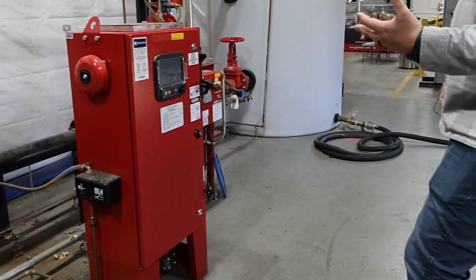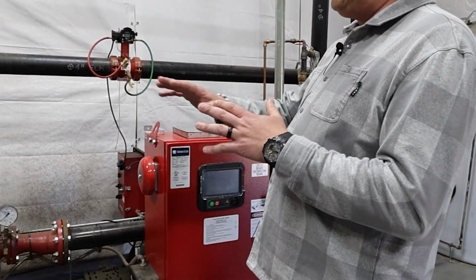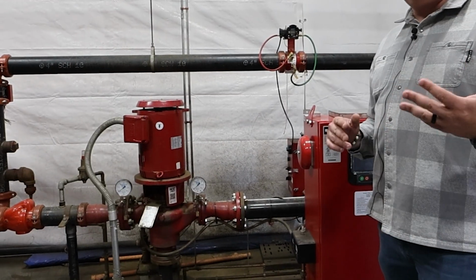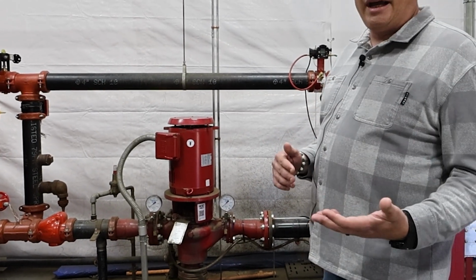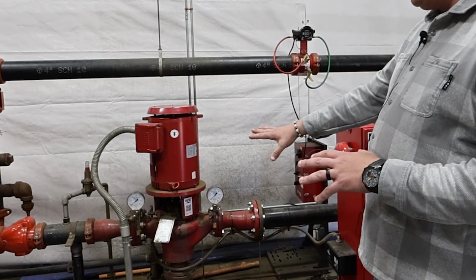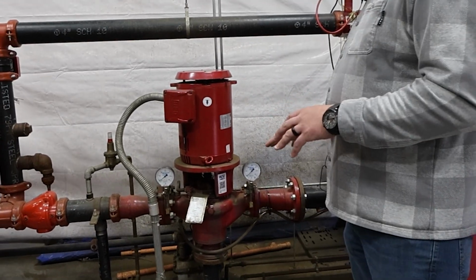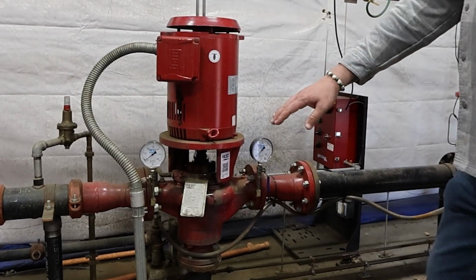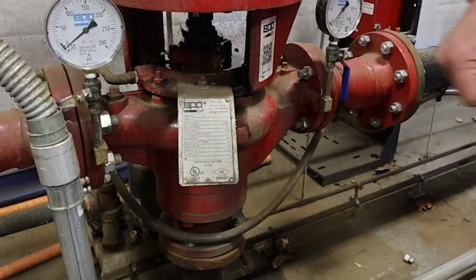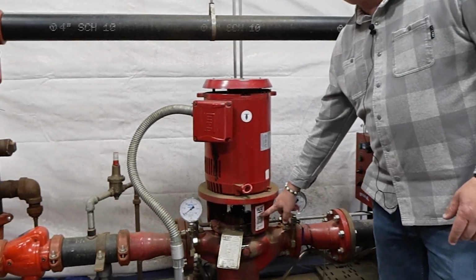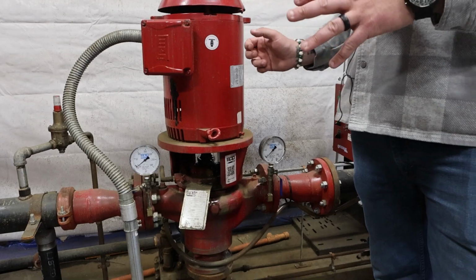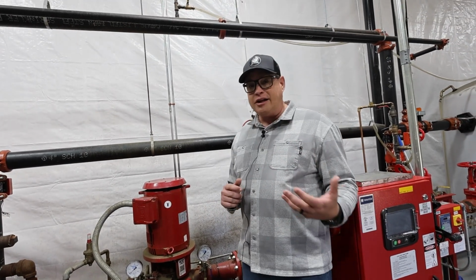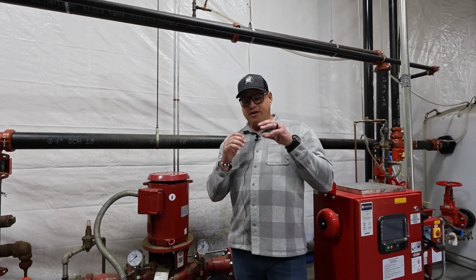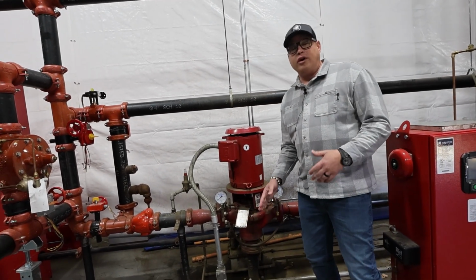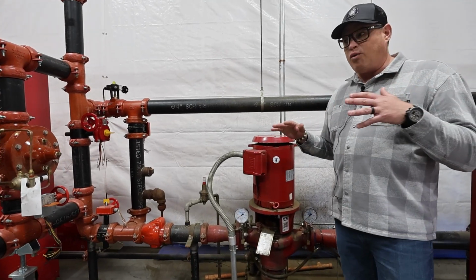The first thing I'm going to do is take a walk around the room. I want to visually see everything, see all the devices, and make sure everything's set up in accordance with NFPA. When I get to the actual pump itself, I'm going to start checking things like gauges, checking my name tape or nameplate here to see what this pump is supposed to do. On SPP pumps, we actually have a QR code, so the pump's information comes up. NFPA 20 clearly states the owner must have a complete set of records for their fire pump — if they don't, they need to get it. Most of the time this nameplate is gone, and we're having to reverse engineer and figure out what this pump is doing.